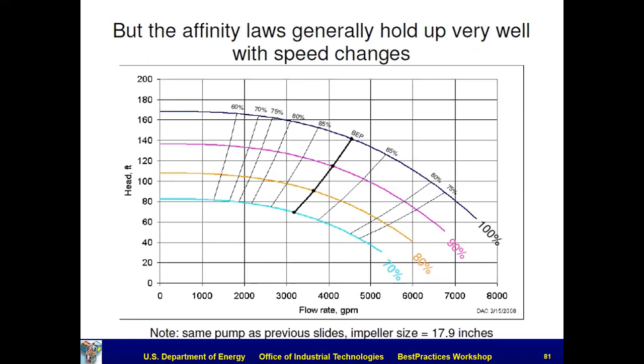And then you say, well, I'm going to scoot this one down a little. I'm going to scoot this one up a little. Well, you do a little engineering on it, and pretty soon you've got this nice smooth pump curve that looks just like the one from the manufacturer. And you've got to realize for his curve, he took 10 pumps and measured the performance and averaged it all together. So the one that you've got, that's been in the field for 10 years, if it's not torn up, if the impeller's not damaged, it's relatively close to this, maybe. So the fact that you've scooted a few points around is really not a problem at all, so long as you don't do something stupid with them.